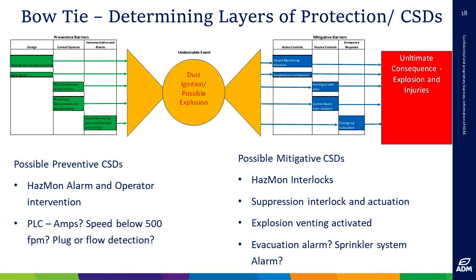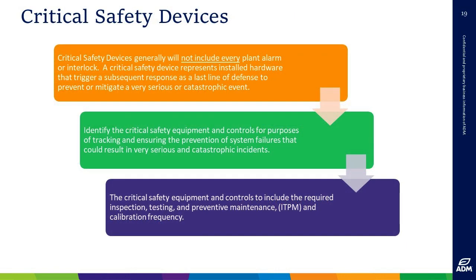That's the critical device. That's the CSD, that alarm. This one's nuisance. That's a problem. But UPS systems, what happens if you lose communication on your HAZMON? We've had that happen. We've had it lose communication and freeze in the current state that it's in. Our bearings are at 90 Fahrenheit. Lose communication. 3 hours later, 90 Fahrenheit. Even if they went to glowing hot.